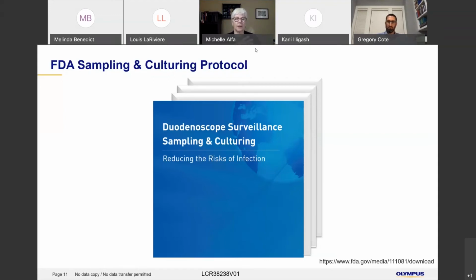So the sample collection itself is shown by the manufacturers to do a good job of extracting the sample from the endoscope channel. And the only one that was targeted in the duodenoscope surveillance sampling and culturing protocol was the instrument channel, so biopsy port to distal end. That's one thing I look for. And the other is the idea that organisms have been through high-level disinfection or sterilization, and they're stressed. There's a phenomenon out there called viable but non-culturable, which means that when organisms are stressed, they go into a mode that is viable but non-culturable. So you can collect them in your sample, but they won't grow because they're damaged. So the idea of having a neutralizer in there to inactivate trace amounts of disinfectant, but also to stimulate the organisms, is cool. And many of the protocols in the past did not do that.